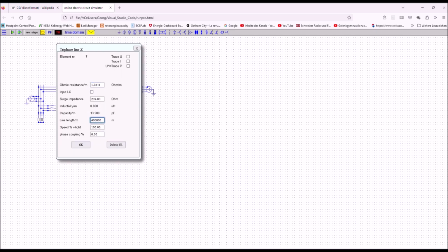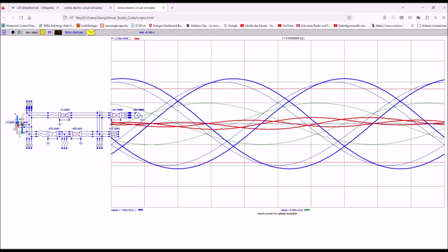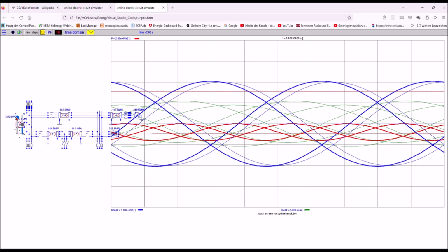Once the network is set up, we enter the right switching sequence to the switches. The sequence shall be triggered by the transient recorder. Let's not forget to set the length of the record. It shall start before the introduction of the short and stop well after the clearance and reconnection of the lines.